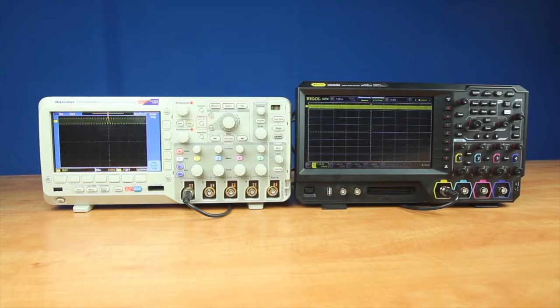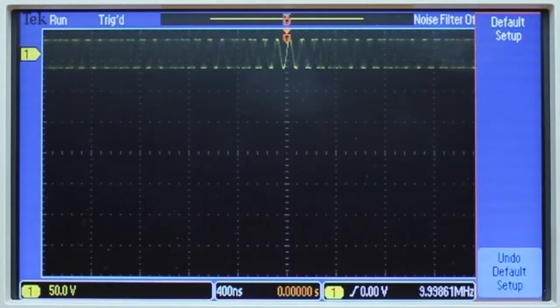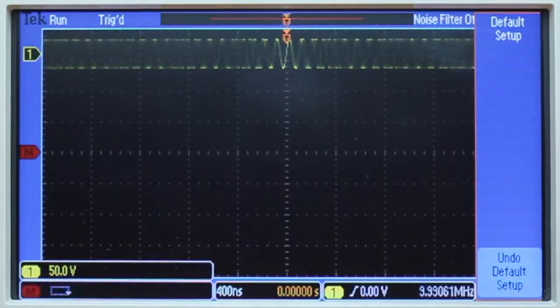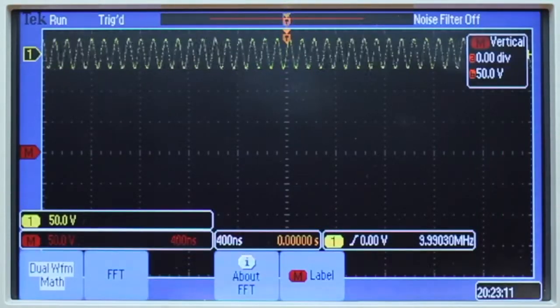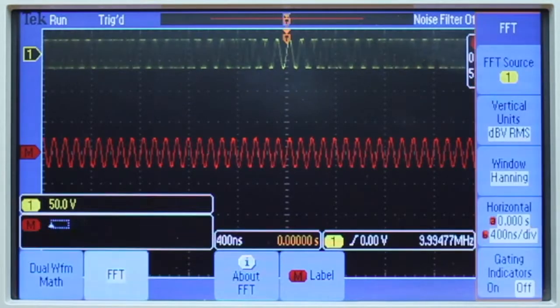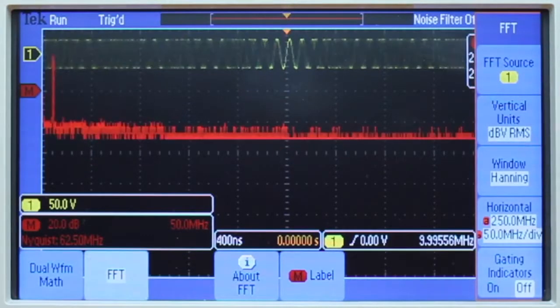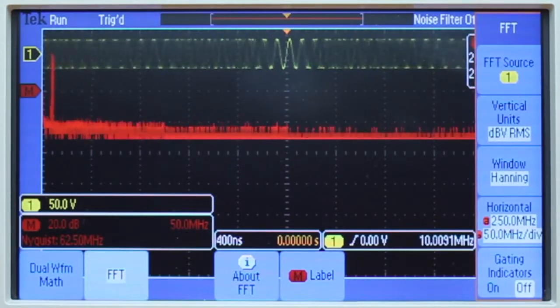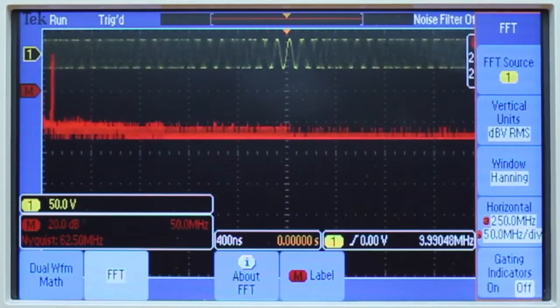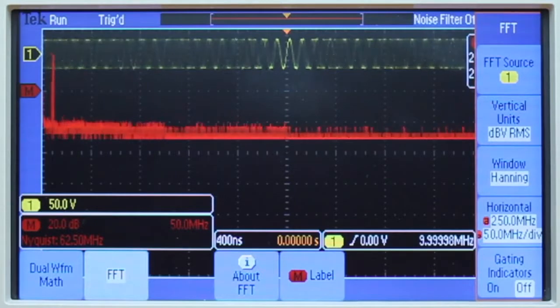To begin with, let's look at the Tektronix instrument. To enter their FFT menu you first press Math and then within the Math menu you press FFT. Once that's on we'll see it in red displayed on the screen.